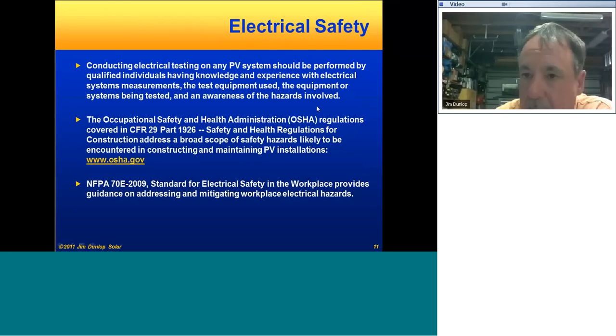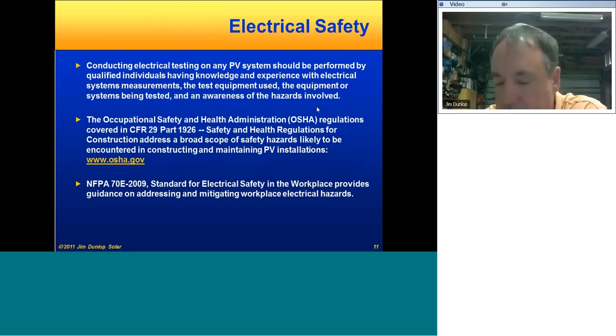One of the things we've got to keep in mind with all this is the electrical safety aspects, and a lot of talk about that lately, and a lot of ramp up with OSHA compliance. And obviously I think people know if they're qualified or they're not, or they're working with people that are and learning from them. They should be familiar with the testing equipment, the measurements. Measurement and testing things is kind of a higher level than just installing stuff. You've got to know what to expect with the measurements and know what to do when something seems to be not correct with the measurement, and be able to verify or determine fault finding and get into the troubleshooting area.